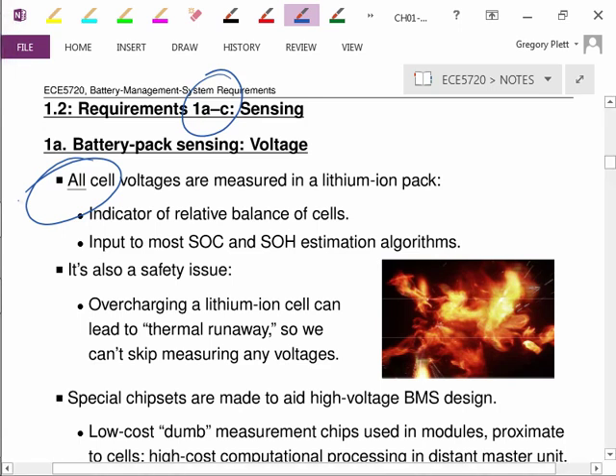For lead acid, you've got your 12-volt battery, which is 6 2-volt lead acid cells in series, and we never measure the 2-volt cells because we don't need to in that case. The technology is leaky and inefficient enough, and can withstand overcharge enough, that we can get away with not measuring all the individual voltages because we can force the battery pack into a stable situation by so-called float charging.